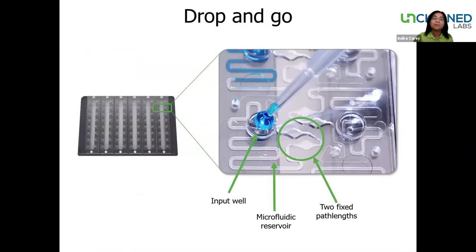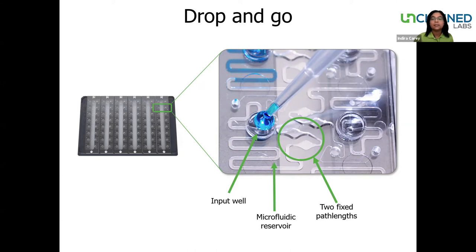So how does our Big Lunatic do all this? Big Lunatic is the only system out there that can measure nucleic acids at high throughput and high concentration. The microfluidic circuit with two fixed path lengths, as you can see highlighted here, covers a wide dynamic range from 0.03 up to 275 OD.